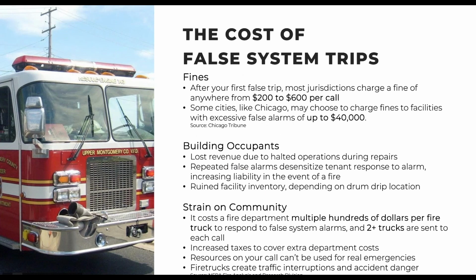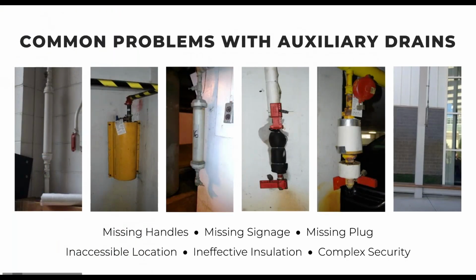In some instances, and this is something we're seeing growing, when these units freeze and break, or they have small cracks in them and they cause air leaks, well, that in turn can trip the system, which may alert the fire department. You get false alarms. So there really isn't a fire event, but the fire companies have to respond. And if that happens due to lack of maintenance on the system, you start to hear about fines being levied on building owners and building management companies for false alarms on their systems. And again, no one wants to waste time there.